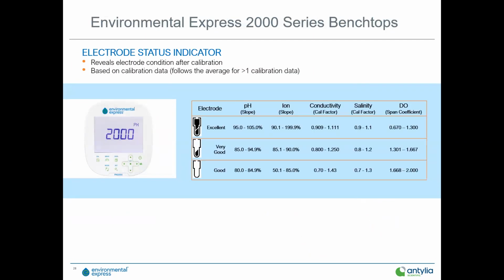So I talked a little bit about the electrode indicator, some of the cool features of the 2000 series. Obviously, it's got the pH slope indicator, as I mentioned. Anything below 80%, you need to refresh the electrolyte inside a refillable electrode, or unfortunately, if it's a sealed electrode, it's probably time to buy a new one. Very good is 85 to 95. 95% and above, that's a killer electrode. That's brand new.